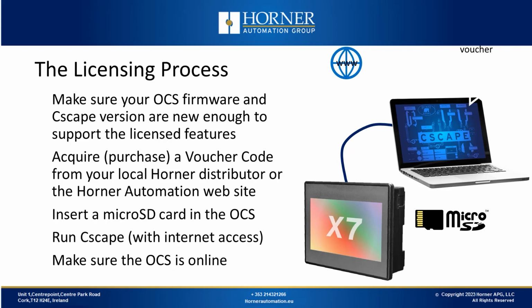Before we begin the licensing process, there are a few things we need to ensure. First, we need to make sure that both our OCS firmware and Cscape versions are up to date. This applies particularly to the micro OCS when licensing beyond WebMI. CANopen and BACnet IP require Cscape Service Pack 9 and firmware version 15.7. Also, you will need the voucher code on the micro SD card we saw earlier. To make the process as easy as possible, it is recommended to have Cscape with internet access. Lastly, ensure that the OCS you intend to license is online with Cscape.